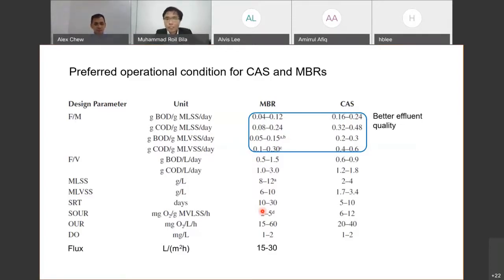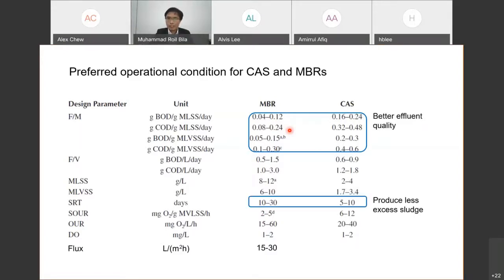Because basically this is the ratio of food to microorganism. So in MBR, we have more sludge inside the reactor, so more sludge eats the same amount of food. That's why the organic concentration in the effluent becomes less. Another thing is that now we operate at a very long sludge retention time.